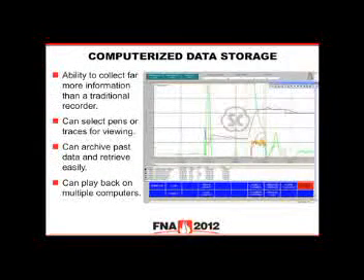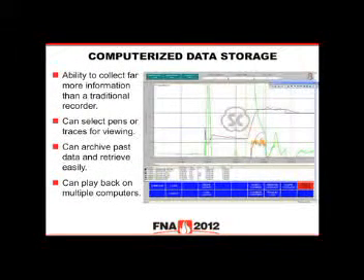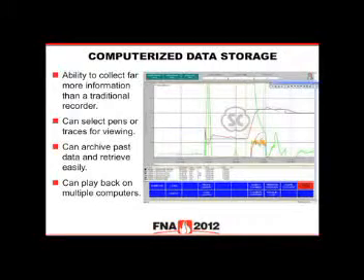On the higher-end systems, there's sophisticated computer data acquisition. The computer collects temperatures, vacuum levels, pressure levels, cycle times, and boost and diffuse data. You can retrieve and play back this data to show customers a good job was done, or scrutinize it if there's a problem with parts to identify and correct furnace issues. These systems also collect all alarms — when they occurred, when they were activated or silenced, who silenced them, and when they cleared.